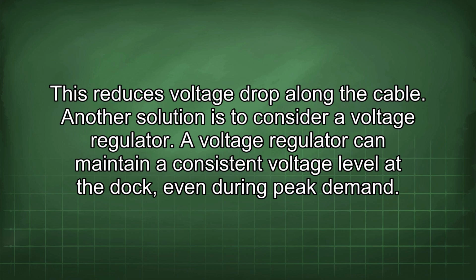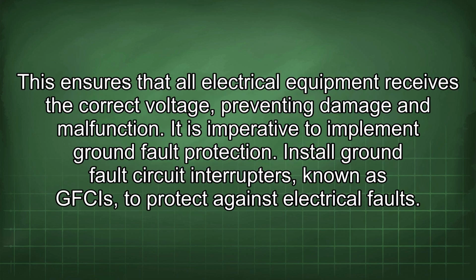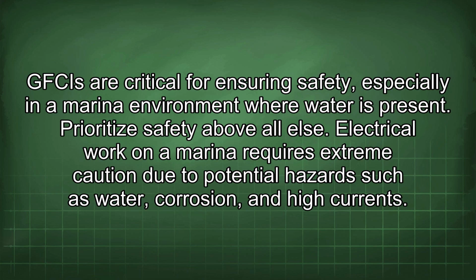Another solution is to consider a voltage regulator. A voltage regulator can maintain a consistent voltage level at the dock, even during peak demand. This ensures that all electrical equipment receives the correct voltage, preventing damage and malfunction. It is imperative to implement ground fault protection. Install ground fault circuit interrupters, known as GFCIs, to protect against electrical faults. GFCIs are critical for ensuring safety, especially in a marina environment where water is present.